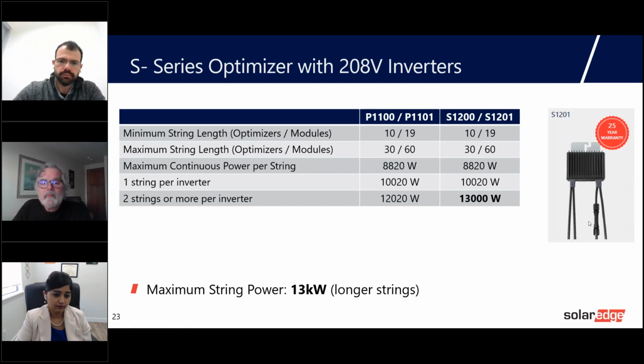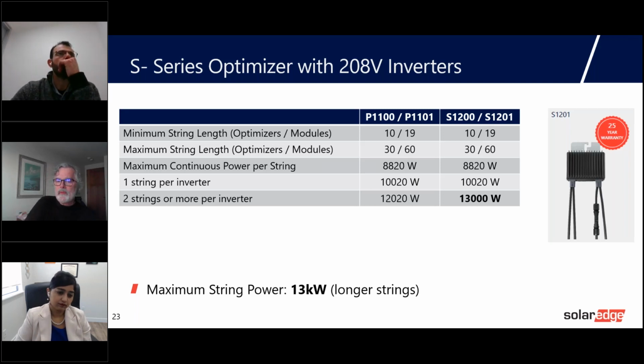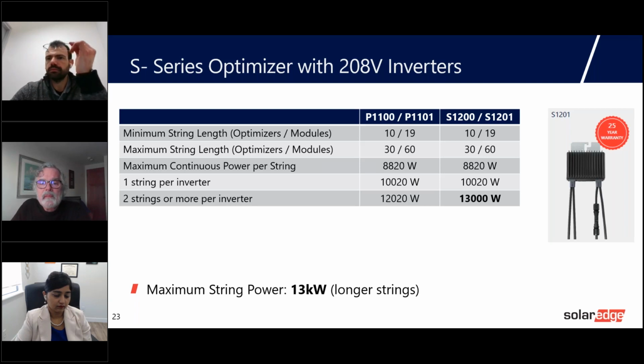However, we do allow string oversizing, and that's what the last two rows here are all about. The row that says one string per inverter is roughly 13 to 15% over the baseline. And this is something we're very comfortable with. It's exactly like a DC to AC ratio on an inverter, typically 15 to 20% over the inverter nameplate rating, just because PV modules rarely produce their maximum power rating, their STC rating. So we're very comfortable allowing you to oversize by 13 to 15%, since it's not very likely that it will actually force the optimizers to limit current with that kind of a power level.